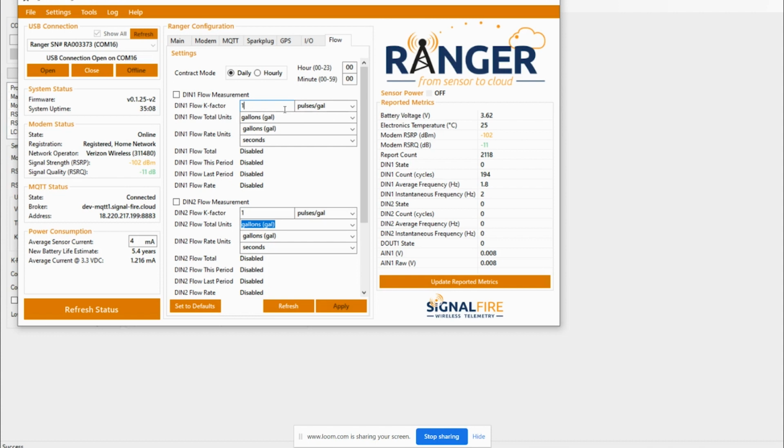Of course, because I set it to 1 gallon per pulse, here it should be considered as 1 pulse per gallon. So here I'm saying for every 1 pulse, consider it to be 1 gallon, which is the reversing match of what I've told the ModQ, where for every 1 gallon output, consider it to be 1 pulse. So that's set up correctly the way that we would like.